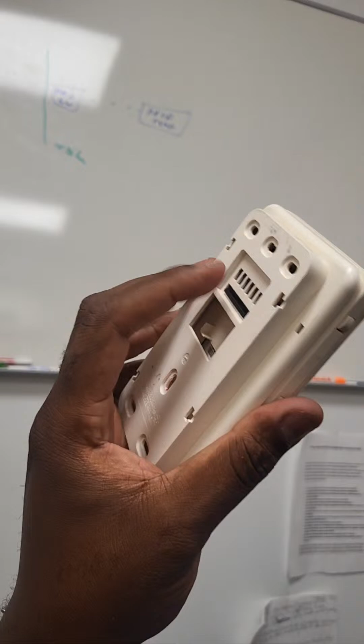If I get the same communicating error after bypassing the indoor thermostat wires, then I'll start first with replacing this thermostat. But if it does work by unhooking the thermostat off the wall and going downstairs, then you'll have to run new thermostat wires. Maybe one or two of your communicating wires are stripped or damaged in the wall.